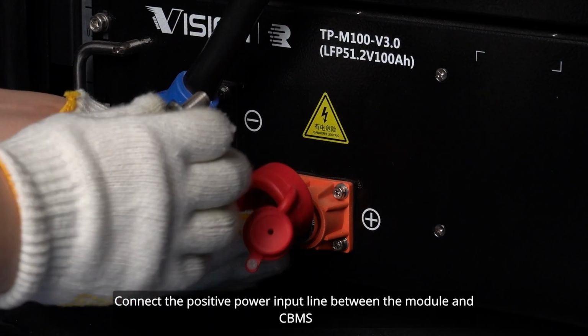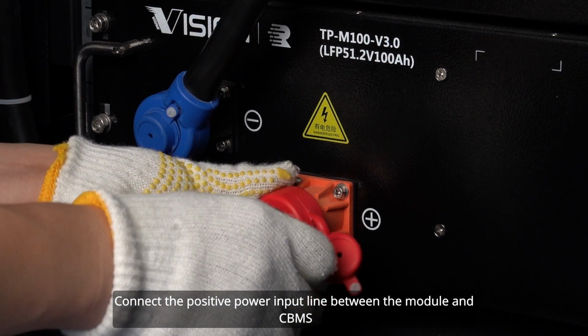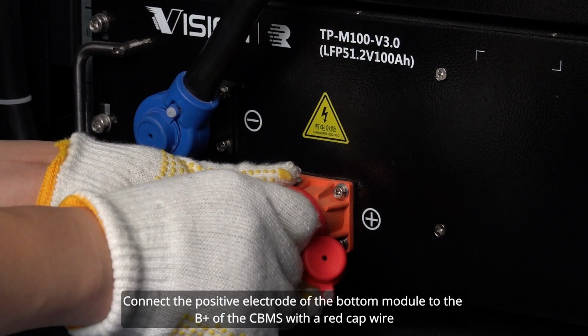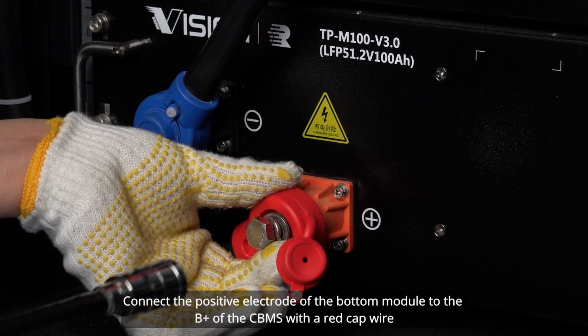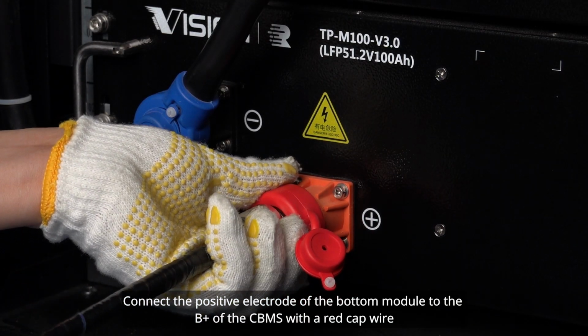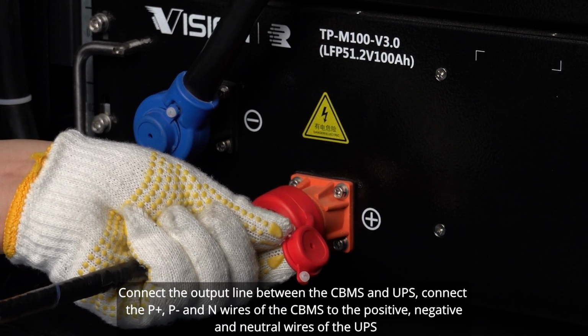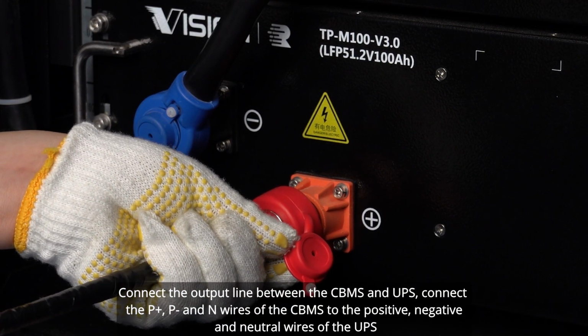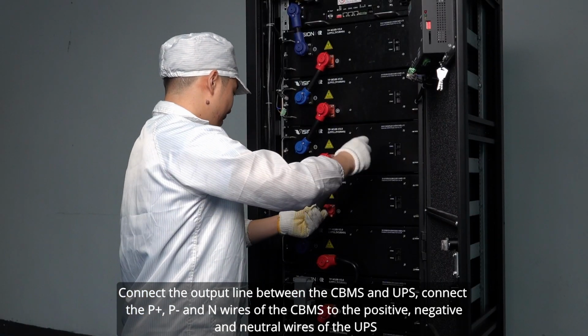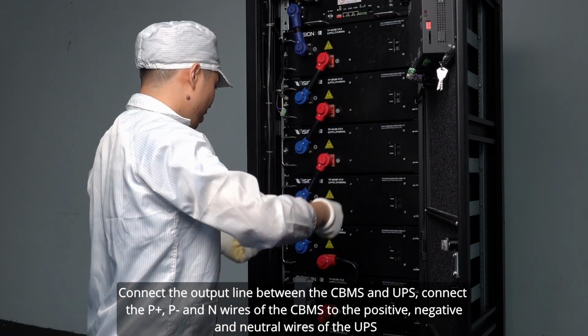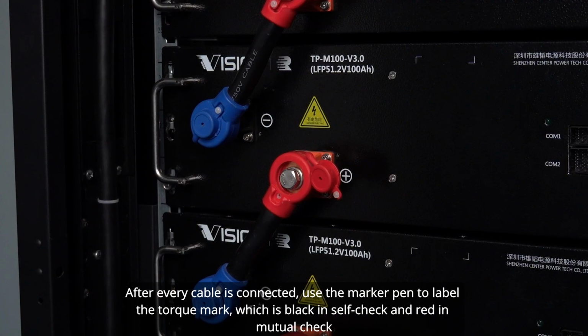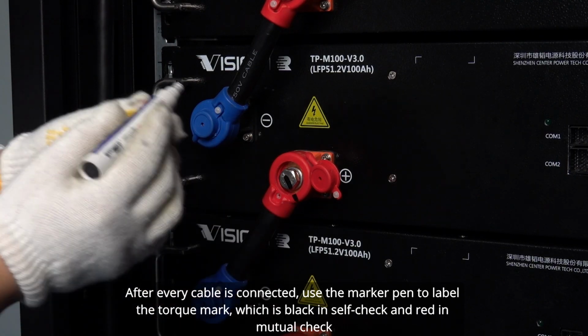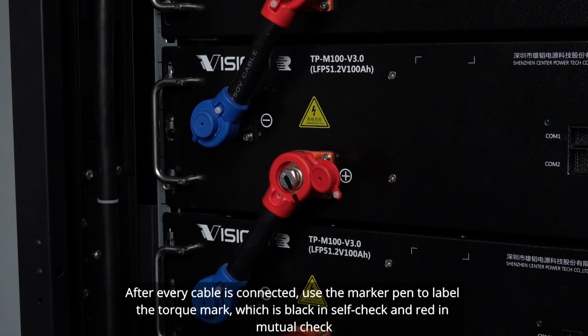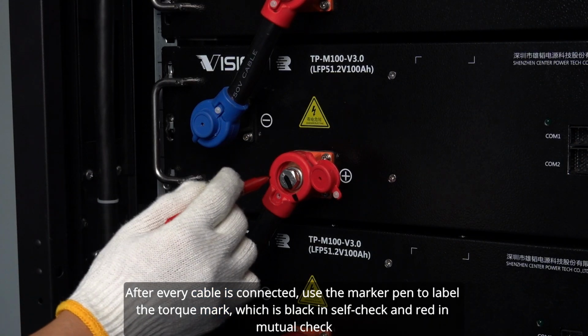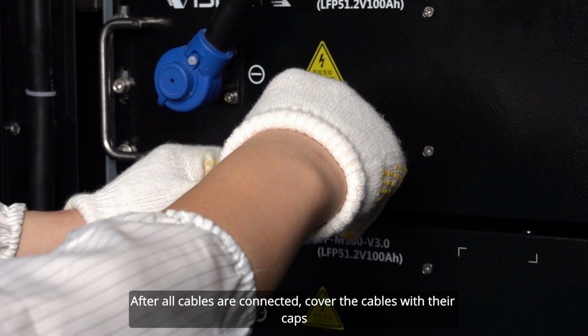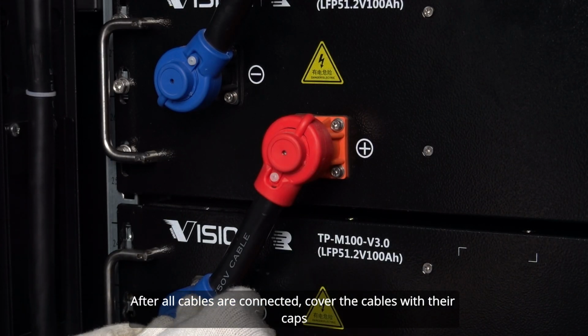Connect the positive power input line between the module and CBMS. Connect the positive electrode of the bottom module to the B+ of the CBMS with a red cap wire. Connect the output line between the CBMS and UPS. Connect the P+, P- and N wires of the CBMS to the positive, negative, and neutral wires of the UPS. After every cable is connected, use the marker pen to label the torque mark, which is black in self-check and red in mutual check. After all cables are connected, cover the cables with their caps.